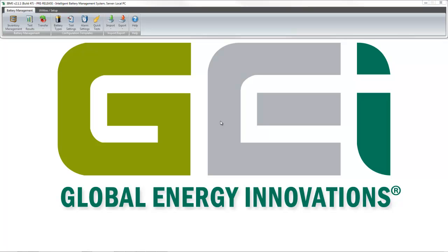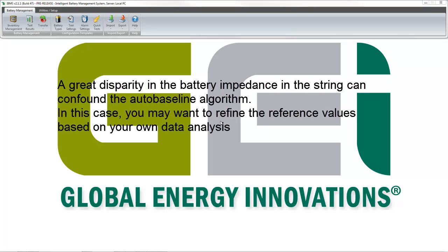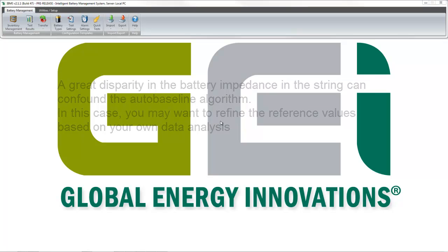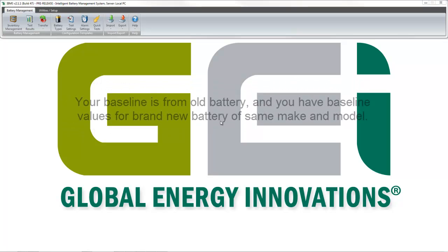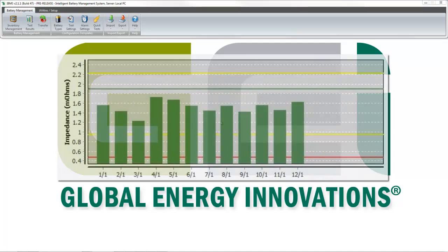The change of baseline values can be detrimental in assessing the health of your batteries. Such adjustments should only be performed when the auto baseline algorithm fails to pick up the right battery, or in other situations such as the baseline values that were originally collected on cells already in service, and you have obtained baseline values from a new cell of the same make and model. In any case, you should not perform a baseline adjustment to artificially make a string appear healthy.